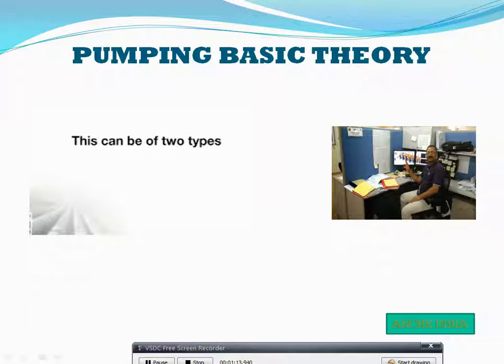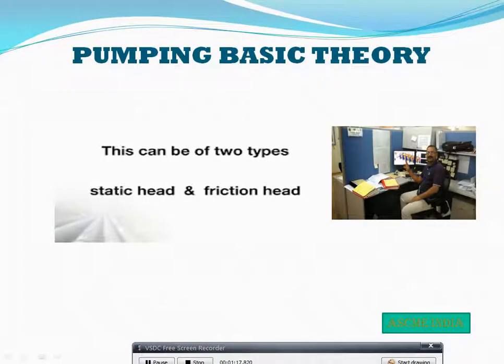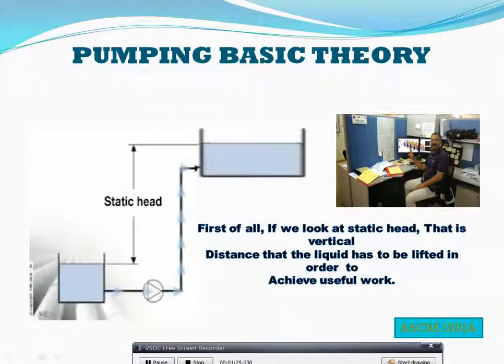Head can be of two types: static head or friction head. Looking at the static head first, that is the vertical distance that the liquid has to be lifted in order to achieve useful work.